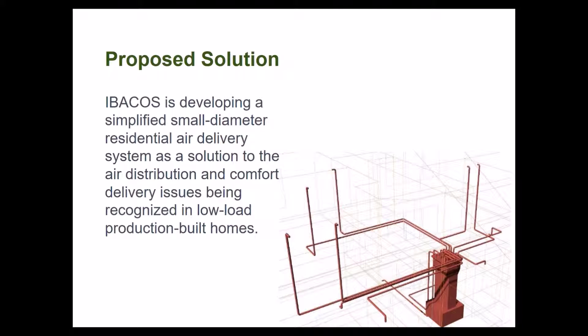There was another suggestion to measure the decibels associated with the new system — going from two-inch ducting and expanding to a larger register. While it's not a thermal comfort issue, it could be conceived as a comfort issue because of noise. It's all part of indoor environmental quality, and it's something we certainly intend to evaluate. We don't want that sort of issue to go unexplored.